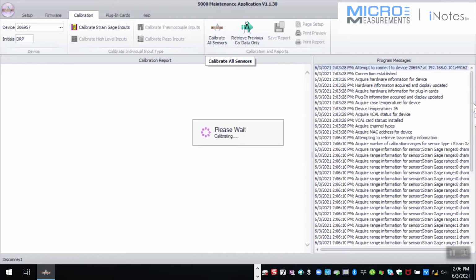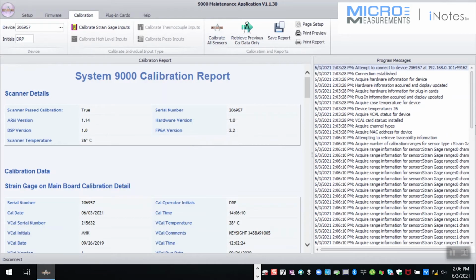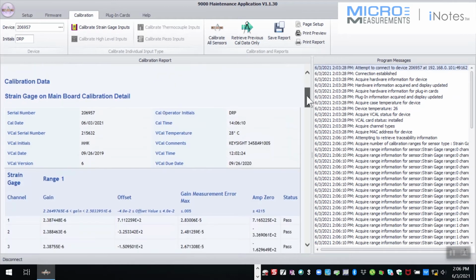And it'll give you an update on the right-hand side of basically everything that it's doing, including when we are connected to the scanner. But what it's going to do is go through a range of voltages across all the channels, multiple ranges, multiple times. It's going to check to see that everything is working as expected. And if it doesn't find the answer that it is expecting, it will fail the test and report back to you. Since the 12 channels of the strain gauges are all contained in the scanner, it's going to be all contained on each scanner.